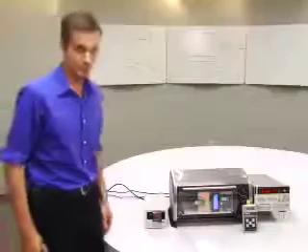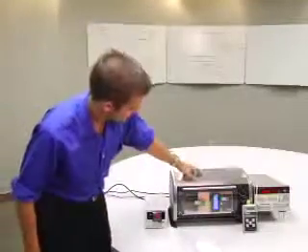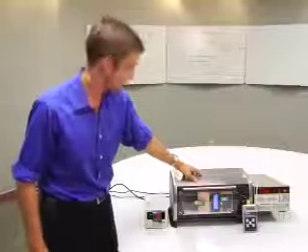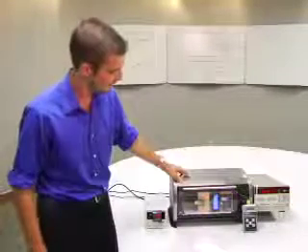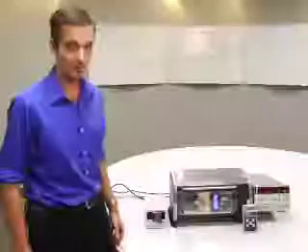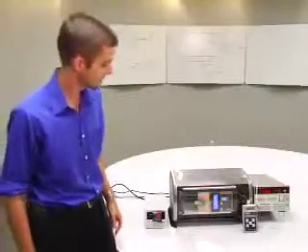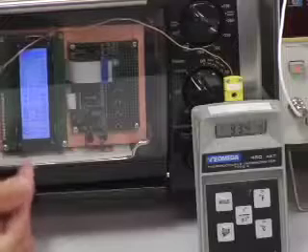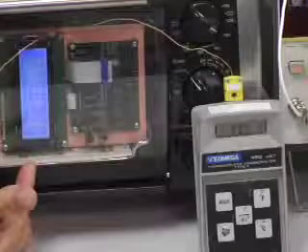It's also a good idea to test unexpected situations. So here we've got the case where the thermocouple meter, or the so-called cold junction, is in an oven at 75 degrees centigrade. And the thermocouple is in a block of dry ice. So that's a way to test out how good your cold junction compensation is. So here you can see the thermocouple temperature is at about minus 89 degrees centigrade.